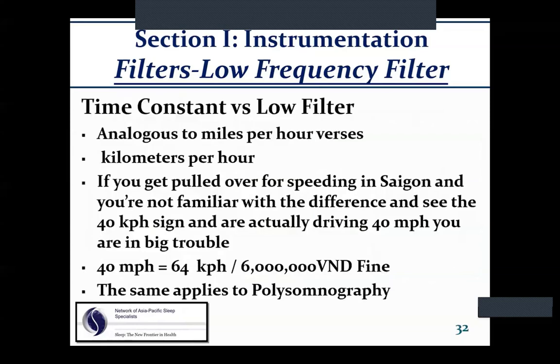Now, some equipment has not low filter settings, but time constant settings. I want to put into context how important it is to know the difference between an appropriate time constant setting versus a low filter setting. Where I see this area of confusion is when a lab converts to a system that uses time constant when they've been using low filter, or vice versa. And I want to give you an analogy about what it's akin to. It's analogous to miles per hour versus kilometers per hour.